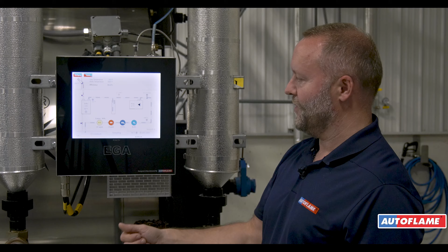Once we've taken all the condensate out of the exhaust gas, we then take that through a series of filters, a pump, through some switches, a temperature sensor, and then we put that gas across the cells. When I say cells, we're talking oxygen, CO2, CO, and NO. They're just the standard sensors.